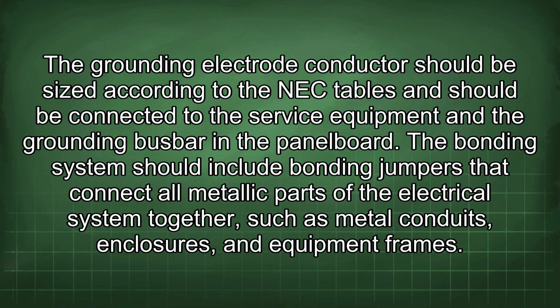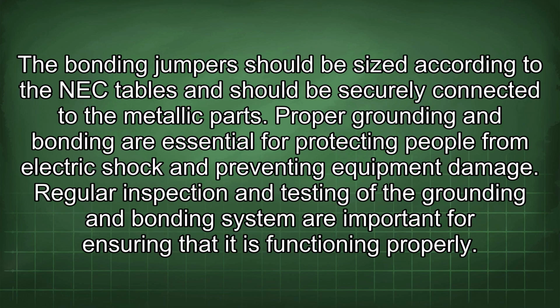The bonding system should include bonding jumpers that connect all metallic parts of the electrical system together, such as metal conduits, enclosures, and equipment frames. The bonding jumpers should be sized according to the NEC tables and should be securely connected to the metallic parts. Proper grounding and bonding are essential for protecting people from electric shock and preventing equipment damage. Regular inspection and testing of the grounding and bonding system are important for ensuring that it is functioning properly.